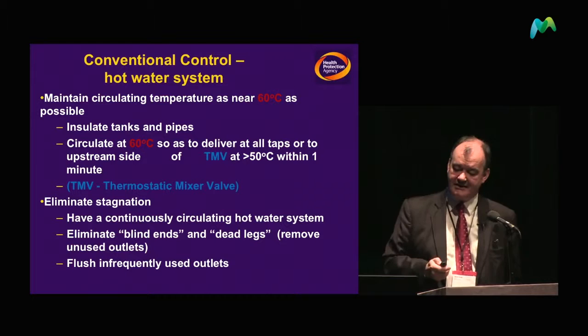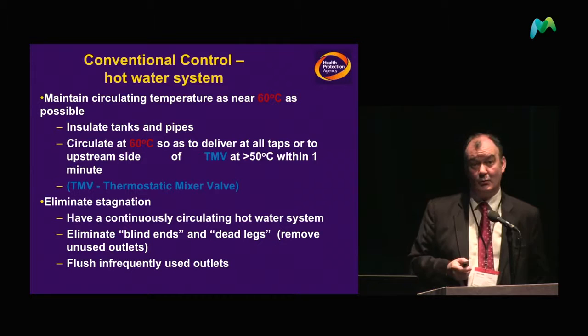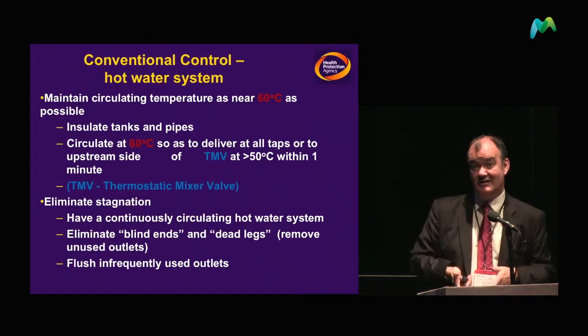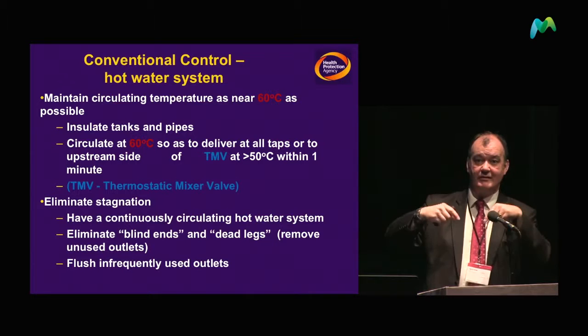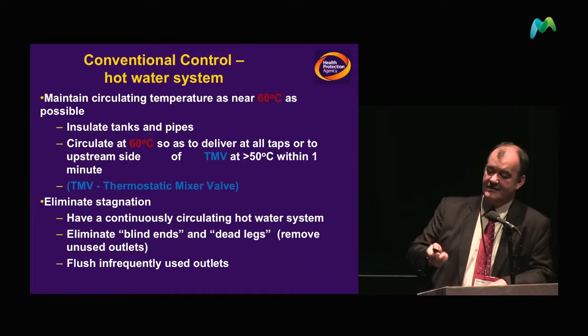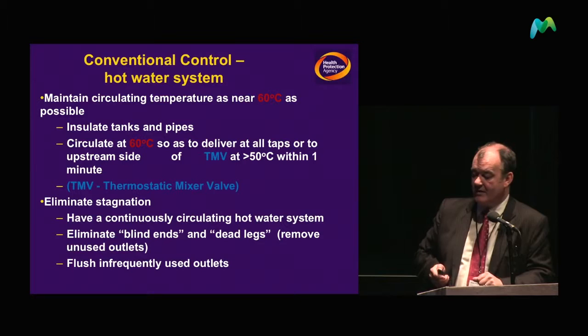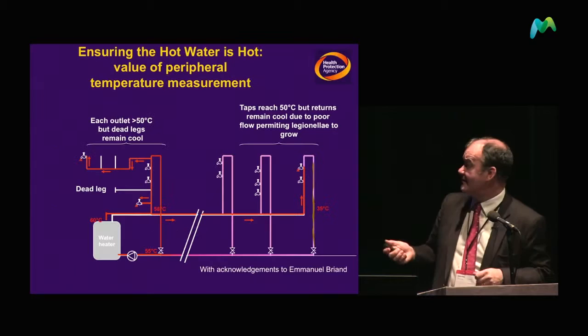The final point in terms of conventional control is about eliminating stagnation. A blind end is something where there is nothing beyond it; a dead leg is a redundant piece of piping still connected, in which you can get material flowing in or out with a drop in pressure. These are the real problem when looking at how to address potential issues in an institution.